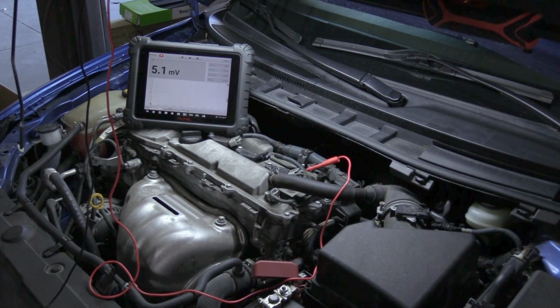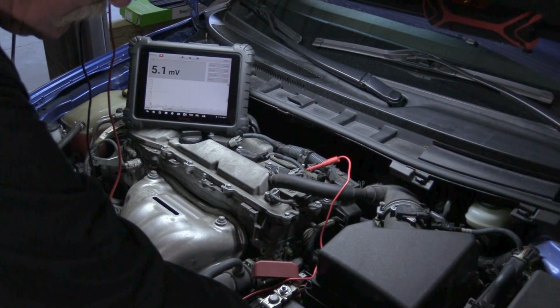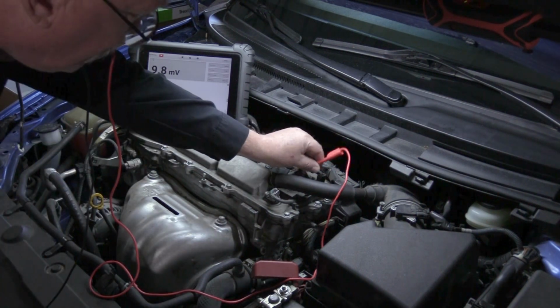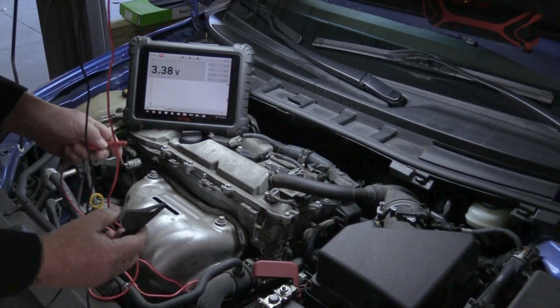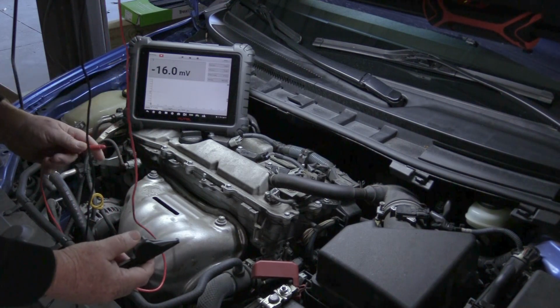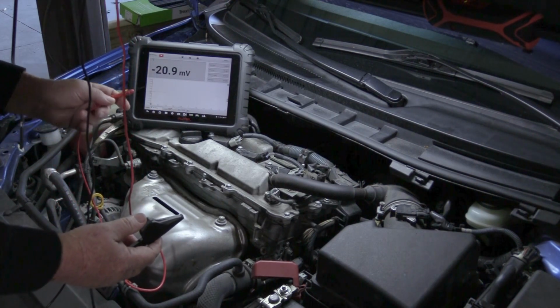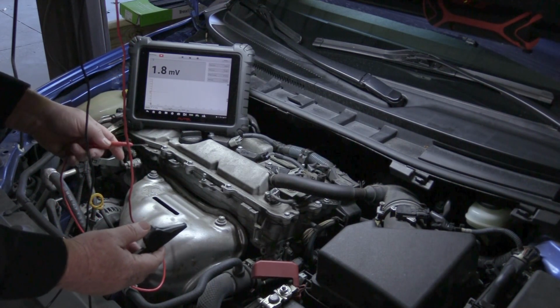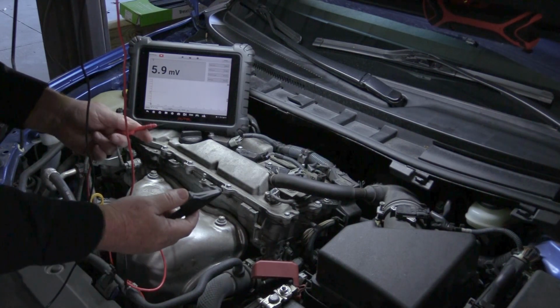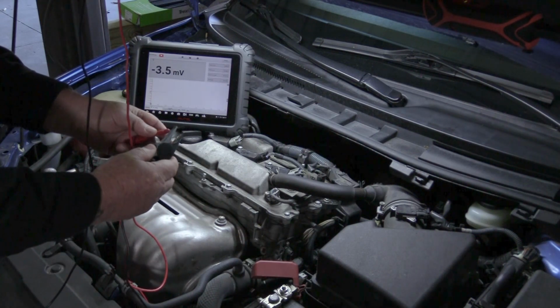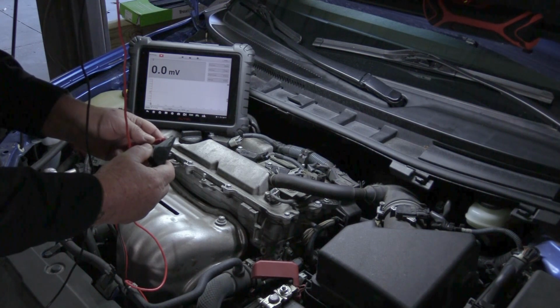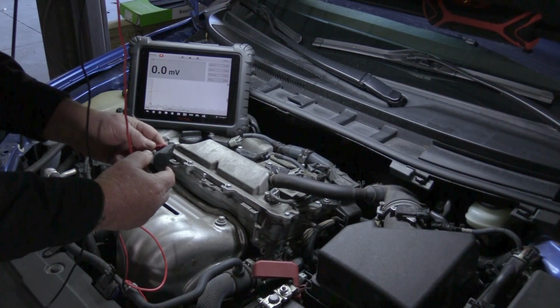Now I want to show you one other thing while we've got the meter hooked up. When I take the meter leads loose, you'll see the leads bounce around a little bit. This is called ghost voltage. It's good to know, because if you see your reading bouncing around, you're not getting good contact with your meter leads. See what happens when I actually put the meter leads together: now it's nice, stable, dead zero. I know I've got good contact with my meter leads, and I'm actually getting an accurate reading. Just something for you to remember.